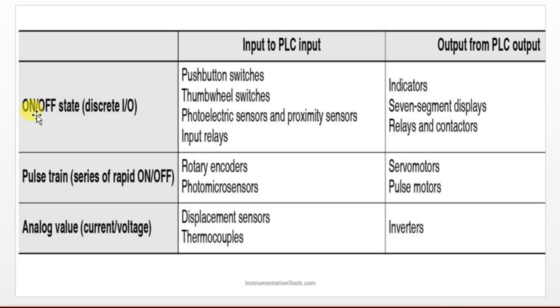For digital IOs, the first type is on/off state. Input devices include push buttons, switches, sensors, and relays. Digital outputs include indicators, lamps, displays, relays, and contactors. For analog IOs, transducers and transmitters come under analog input, while VFDs, inverters, and control valves are analog outputs. For pulse IOs, encoders and photo micro sensors are pulse inputs, and servo motors and pulse motors are pulse outputs. Depending on the IO type, we choose the IO modules.